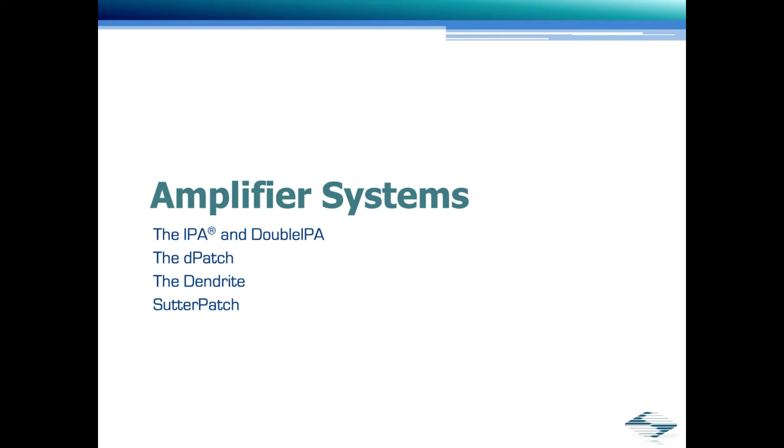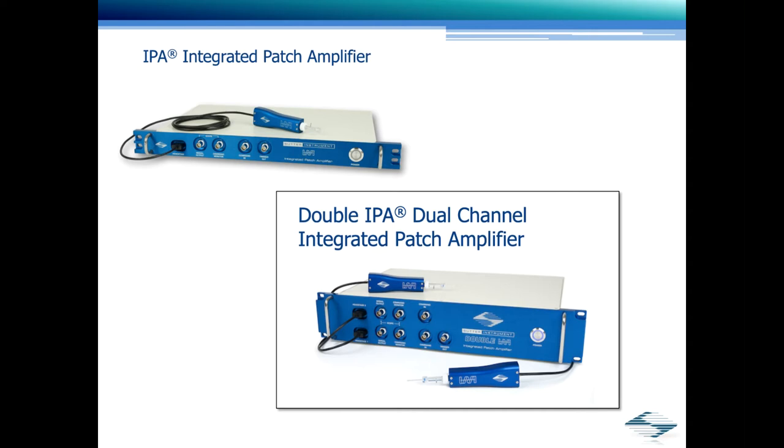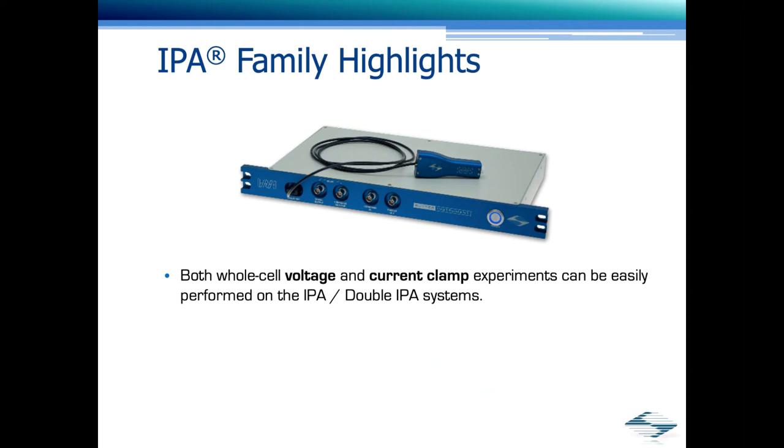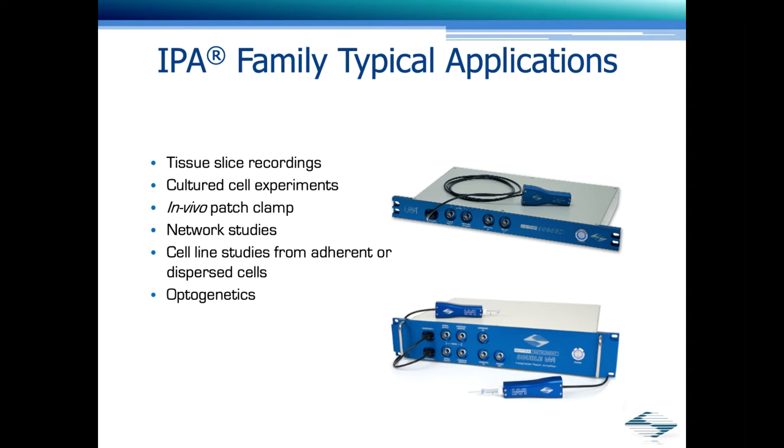The final piece of the puzzle is our amplifier system. Sutter has a couple of options for those as well. The feature set of the IPA will meet the requirements for the bulk of our customers. The IPA is available in either a single head stage or dual head stage configuration. Typical highlights include whole cell voltage and current clamp experiments. Fully integrated patch clamp amplifier with data acquisition system. And includes the Sutter Patch data acquisition software. These are some of the applications that the IPA is well suited for: tissue slice recordings, cultured cell experiments, optogenetics, name a few.